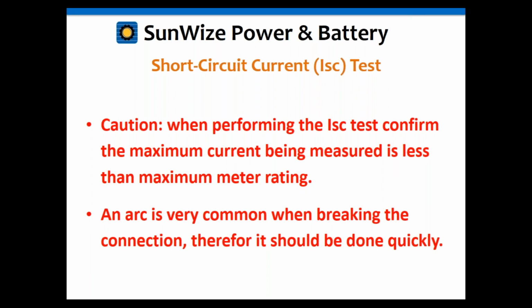Most solar modules can have a short circuit current of up to almost 10 amps. Some of them now are at 9.2 amps or so, some of the bigger ones. So we need to make certain that you have equipment that can measure that without damaging it. Again, most multimeters are good up to 10 amps, so you should be fine, but make certain that your multimeter can handle that and that you have your probes and your leads set correctly for that.